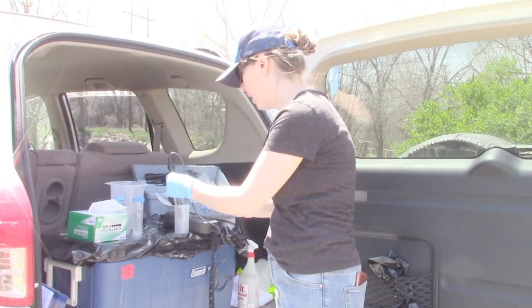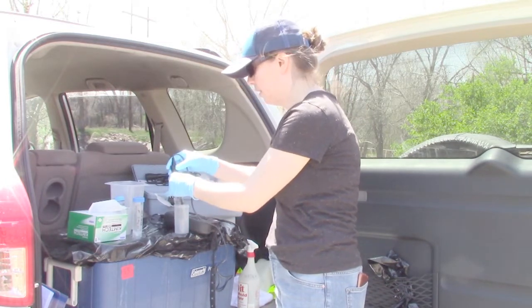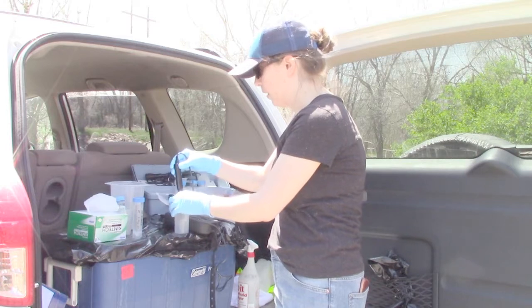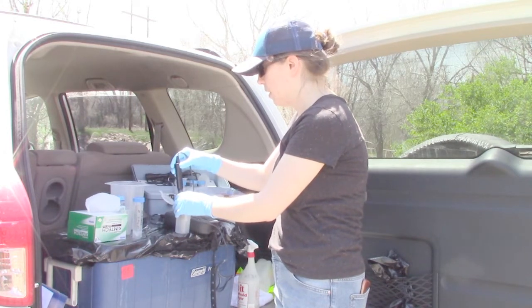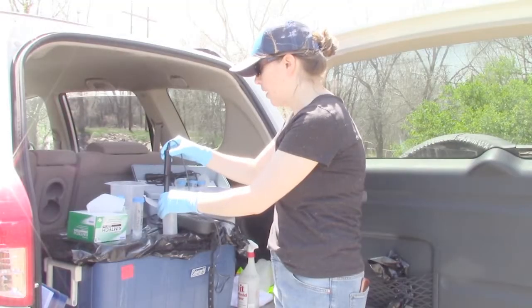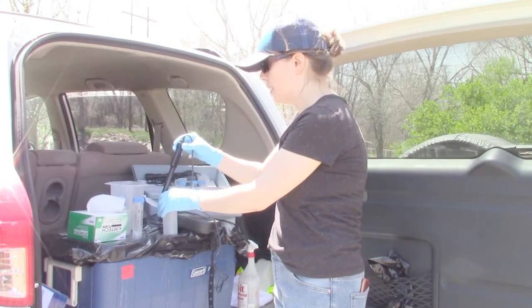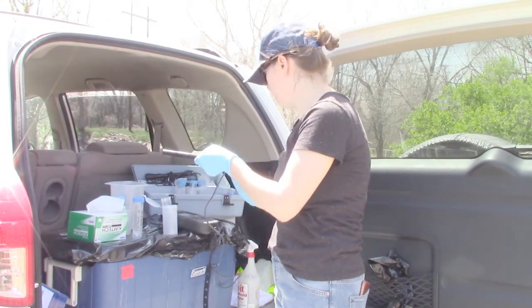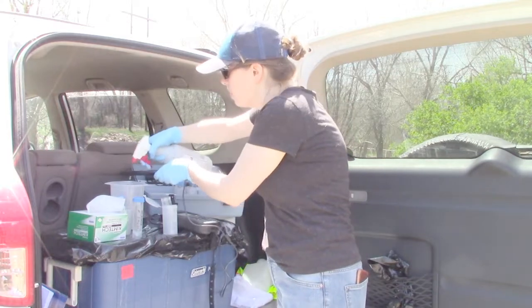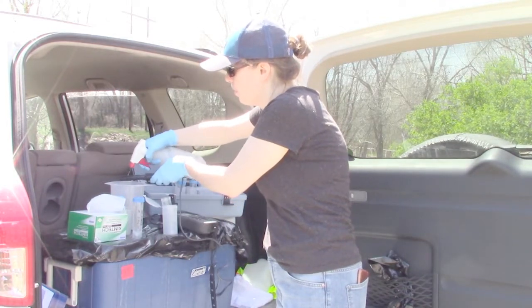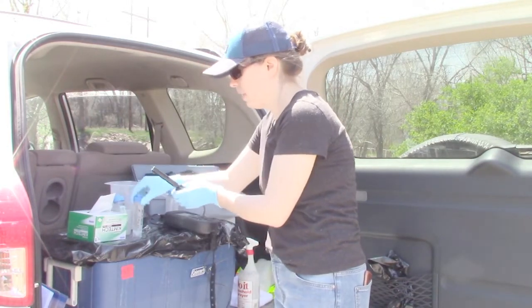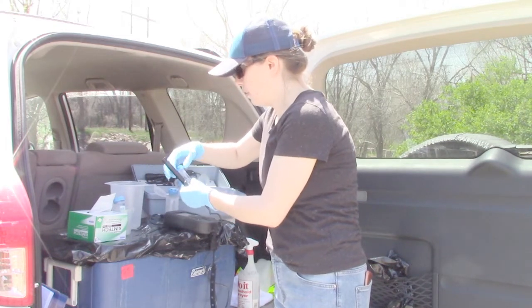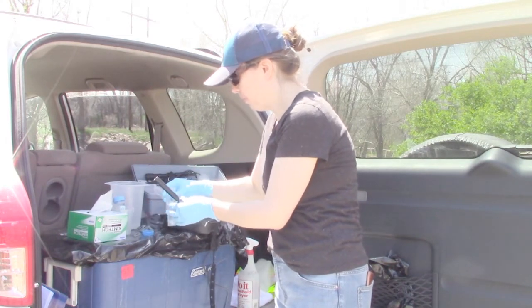So we go to calibrate and then press read. This might take a while to stabilize. The value it's stabilized at is 1378 microsiemens per centimeter. So that's close enough. Now let's see if it can give us a reading for the sample.